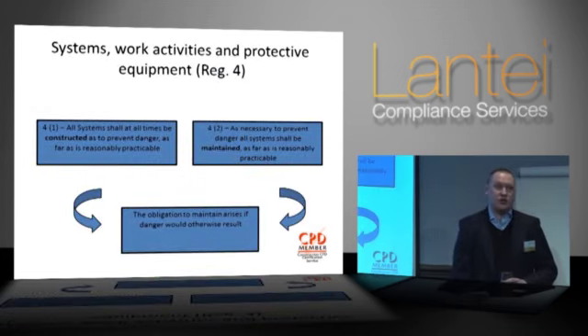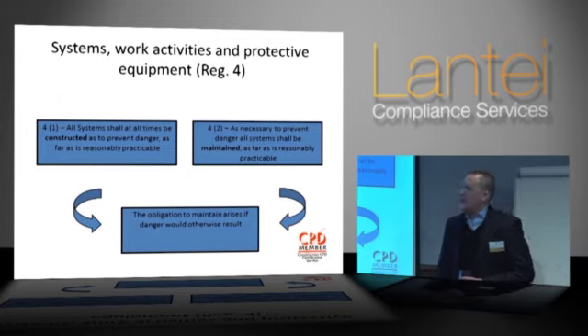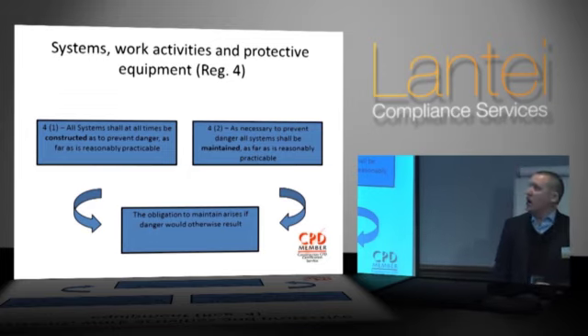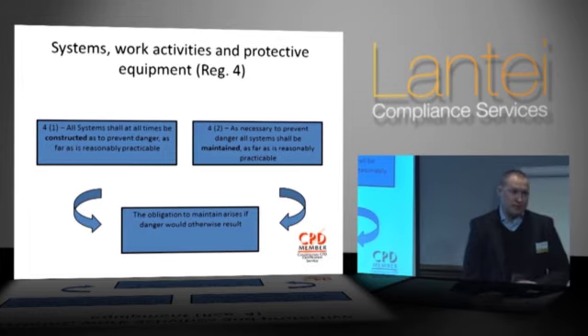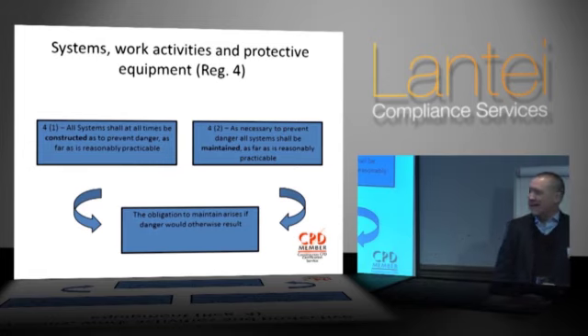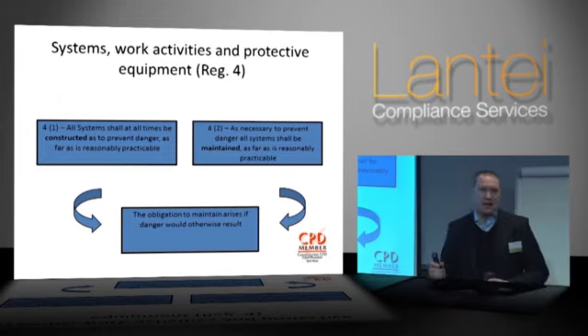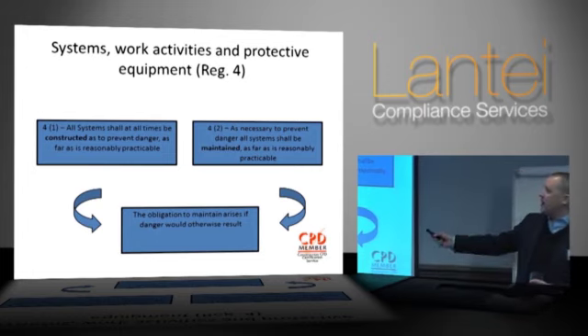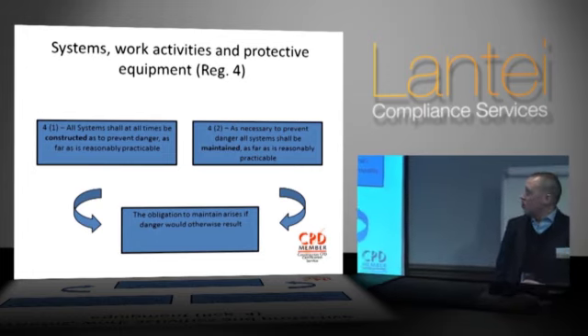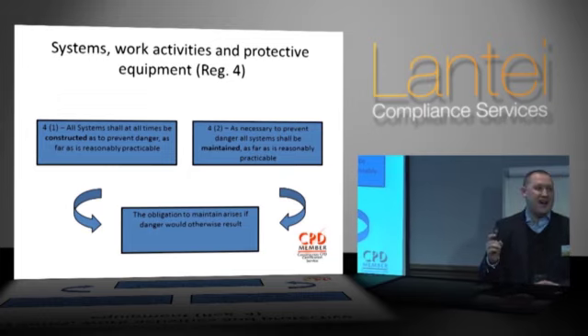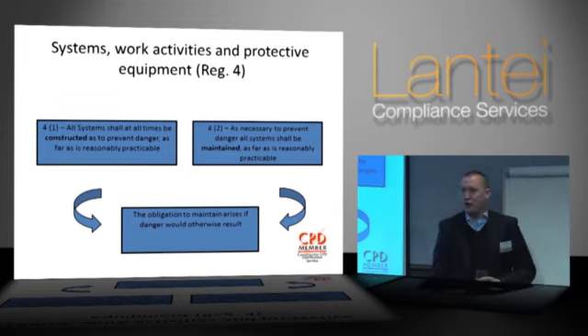So let's come back to the Electricity at Work Regulations. When we look at Regulation 4, it talks about systems, work activities and protective equipment. There are two real main parts to this Regulation 4. Regulation 4.1 clearly says that all systems shall at all times be constructed so as to prevent danger as far as is reasonably practicable. Regulation 4.2 says that, as necessary to prevent danger, all systems shall be maintained, again as far as is reasonably practicable. And then we've got this statement: the obligation to maintain arises if danger would otherwise result.